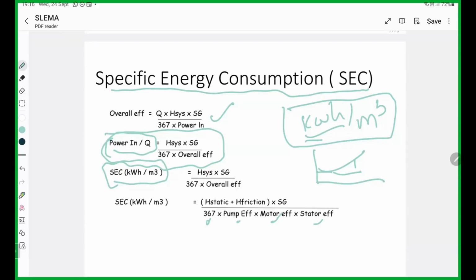Very simple. In energy conservation, what we have to do is reduce this specific energy consumption. That is the ultimate goal in a pumping system. If you can reduce the SEC, then you can save energy, right? This is the basic equation. If you want to reduce this SEC, then you can see here you have to reduce static head, you have to reduce friction, and you have to increase pump efficiency, increase motor efficiency, and increase starter efficiency. That's all. Very simple. If you want to save energy, you have to reduce static and friction and increase pump efficiency and motor efficiency. But the problem is how we can do this practically in a centrifugal pumping system, right?